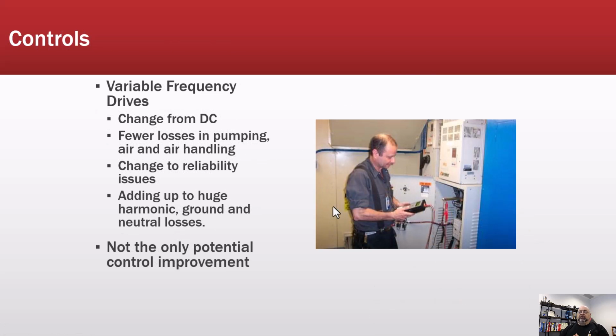Controls such as variable frequency drives, changing from DC, using it in the application of pumps and fans and everything else, changes our reliability issues. A lot of times it'll move some of the problems we're having from elsewhere in the system back to just the motor and pump, or motor and fan, or motor and compressor. However, what we seem to forget is harmonic content adds up in a system.